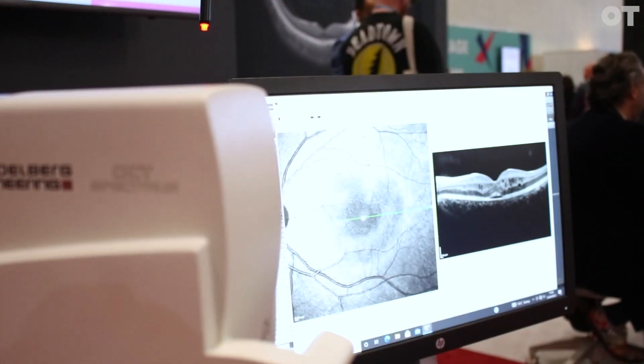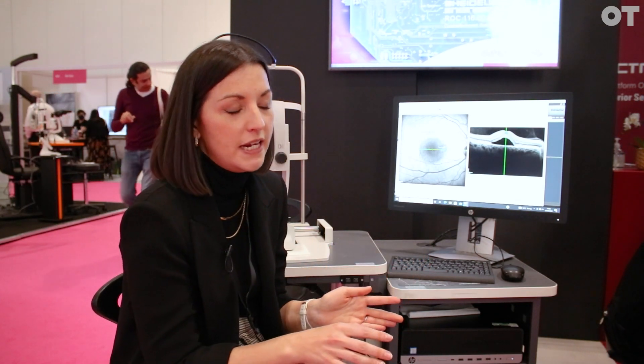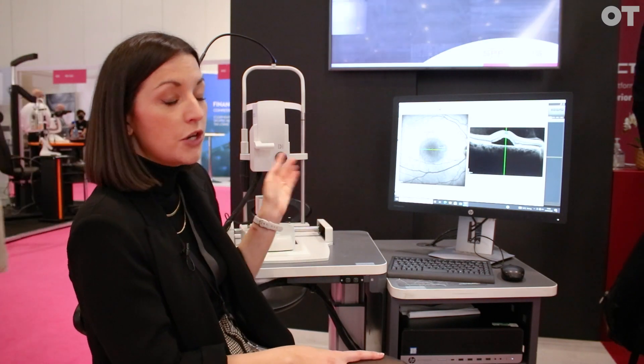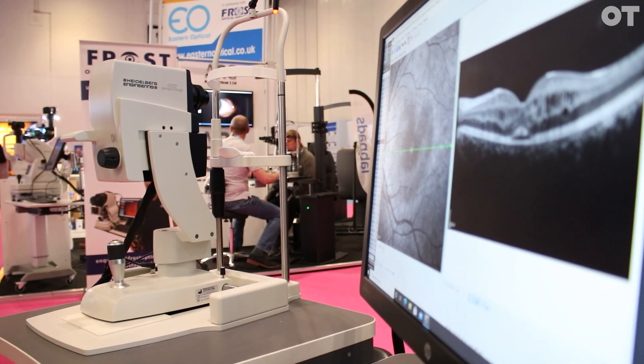We have recently launched the Spectral Shift technology, which allows us to increase or decrease the A-scan rate. We can decrease it down to 20 kilohertz — a slower scan speed — giving a longer exposure time when imaging the eye. This helps build images in more challenging patients, for example those with a media opacity like a cataract, producing a nicer higher-quality image. We can also speed up to 125 kilohertz, which is great for dense scan patterns such as OCTA, getting about 30% quicker speed than before.